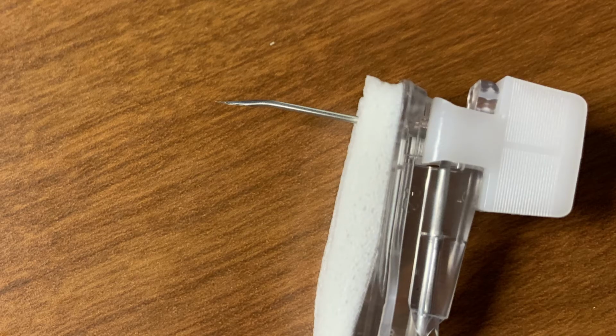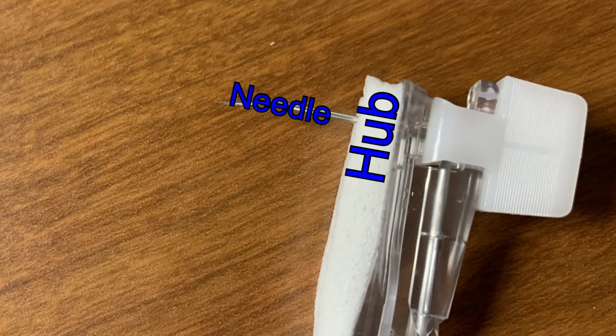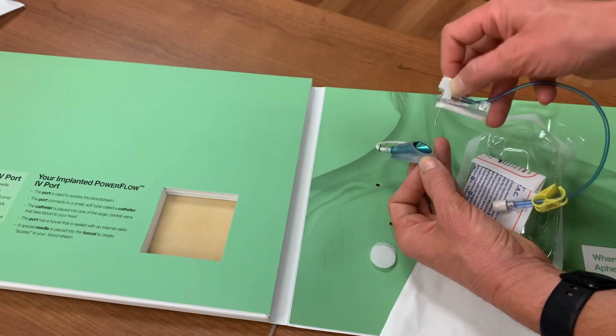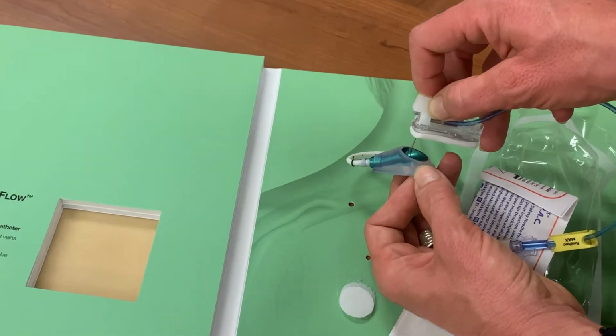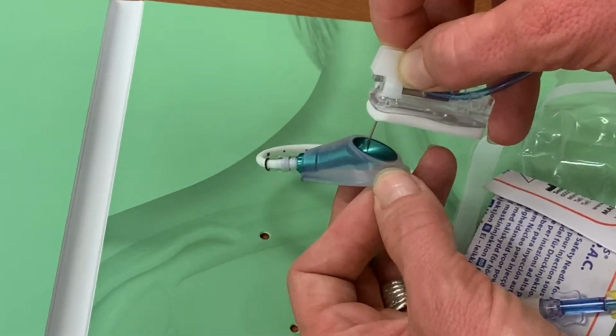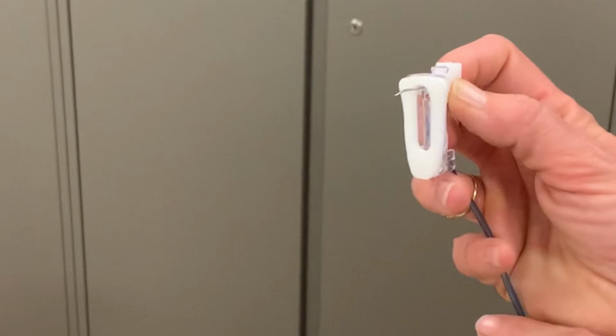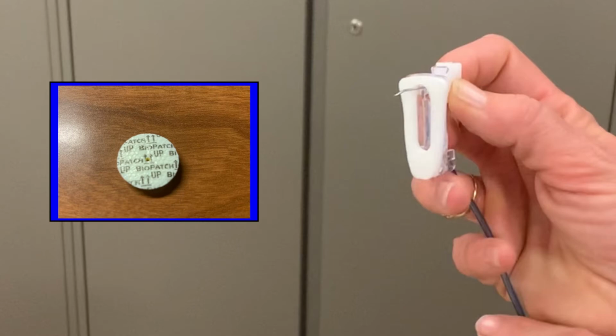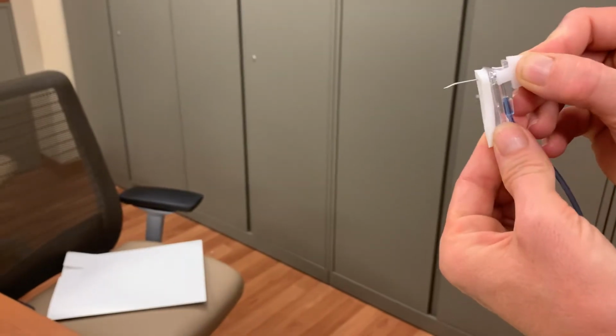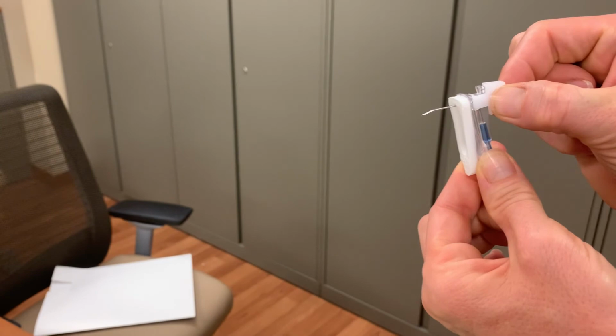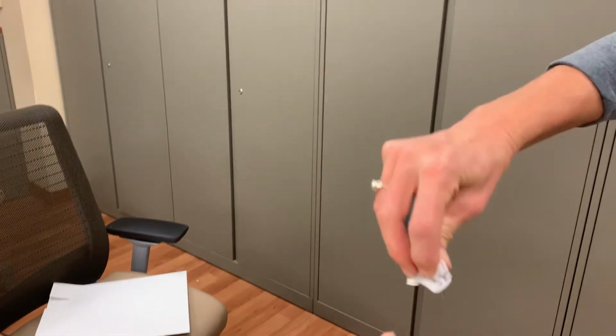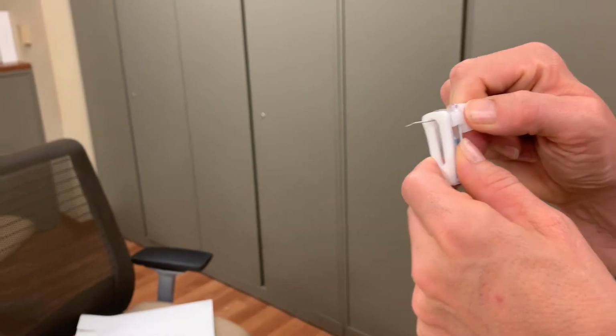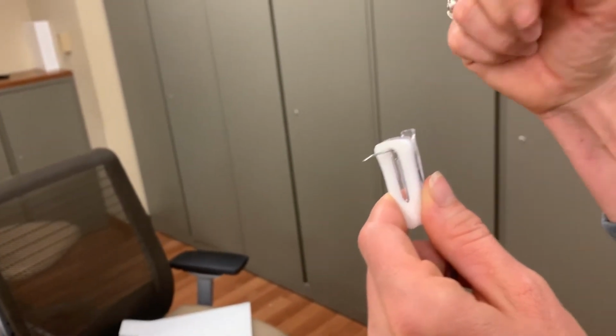Both needles are designed the same. The needle is oriented perpendicular to the hub. These are used to access the port by pressing them straight down onto the port. The goal is to get the tip of the needle past the port's membrane and resting inside of the reservoir. Around the needle, on the base of the hub, is a foam pad. This serves only to prevent pressure injury on the patient's skin. It does not have any disinfectant quality, so you will be applying a biopatch under the device for the purpose of disinfecting. On the back of the device are small tabs to be used as handles to stabilize the device during insertion. Once in place, the tabs should be removed by squeezing them together. They will release from the hub like opening a chip clip.